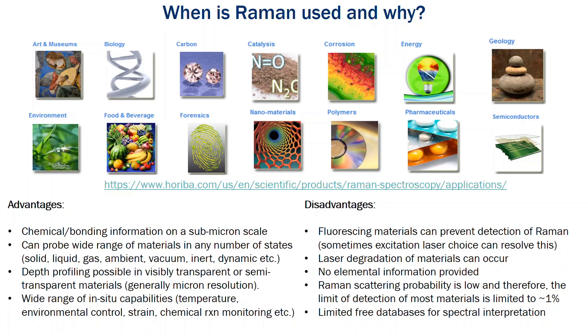Some of the disadvantages: fluorescing materials often will drown out the Raman signal, though this can sometimes be avoided by selection of the excitation laser. The laser itself can sometimes degrade the material, so you have to be careful about the power you use when doing your scans. There's no elemental information provided from this technique. Raman scattering is also a low probability light interaction, which historically was a hangup, but our ability to detect the light has improved over the years. The limit of detection for most materials is around 1%, though that can change depending on circumstances. There are also a limited number of free databases available for spectral interpretation, which can make that challenging.